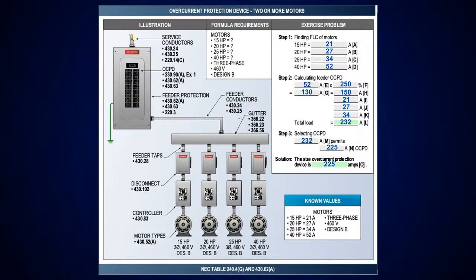Then you're going to go look at table 430.52C1. You'll pick up for an inverse time circuit breaker, which is what we're sizing here. And you come across, it'll tell you take it at 250%. And then you take that 250%, that gives you 130 amps, and go up to the next standard size, which is a 150 amp overcurrent device.